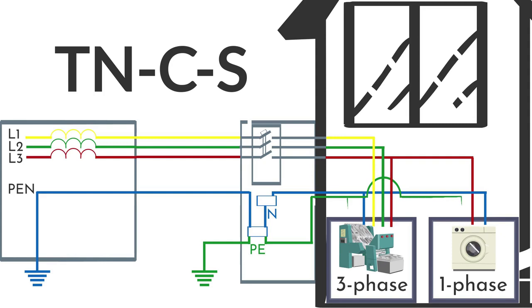All the domestic appliances are connected by means of a conductor through the PE bus. In this way, a four-core wire consisting of three phases, L1, L2, and L3, and a PEN conductor is used into the domestic input device in the TN-CS system, while five-core wire consisting of three phase, N, and PE conductors enter the house.